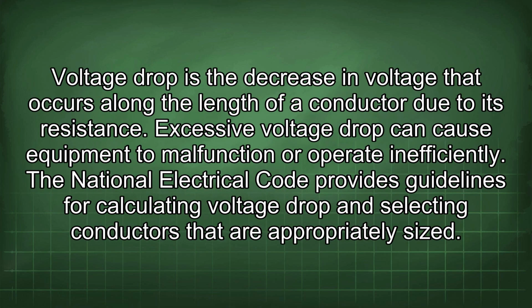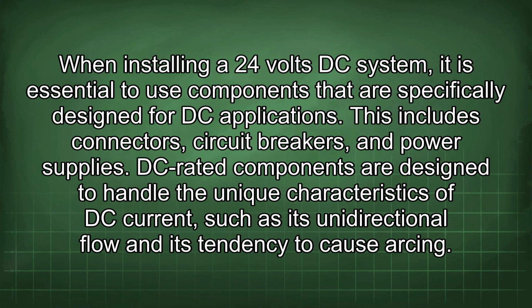Voltage drop is the decrease in voltage that occurs along the length of a conductor due to its resistance. Excessive voltage drop can cause equipment to malfunction or operate inefficiently. The National Electrical Code provides guidelines for calculating voltage drop and selecting conductors that are appropriately sized. When installing a 24 volts DC system, it is essential to use components that are specifically designed for DC applications. This includes connectors, circuit breakers, and power supplies.